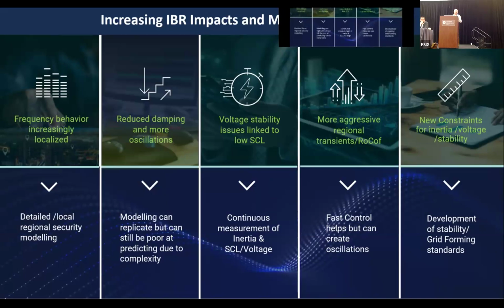The system, related to its impedance and the machines on it, has a natural resonance which you can see all the time in the frequency, and they just start talking to each other. Sometimes that goes wrong and you get an oscillation off the back of it. For every one big oscillation, you will find hundreds of micro oscillations in the data, telling you that you have an increased risk of a main oscillation.